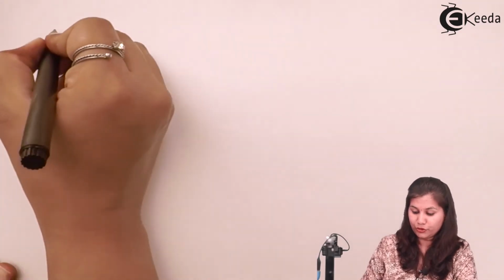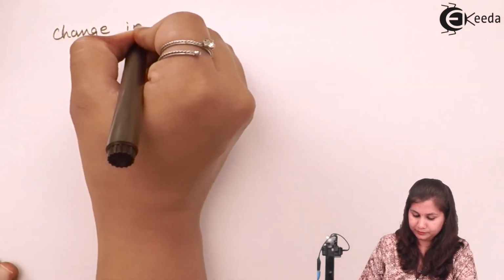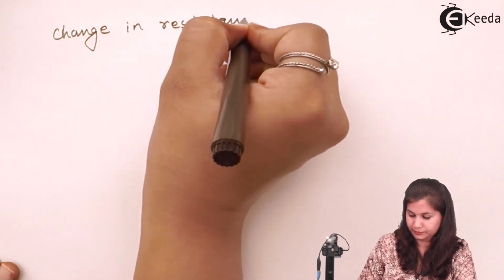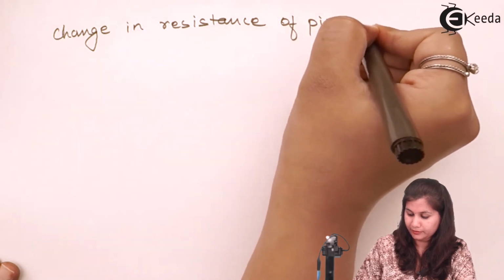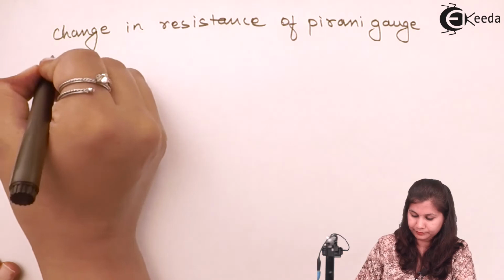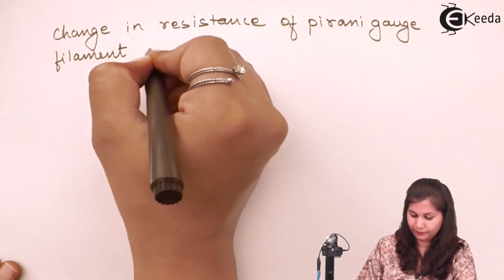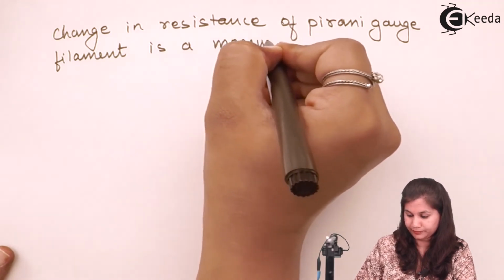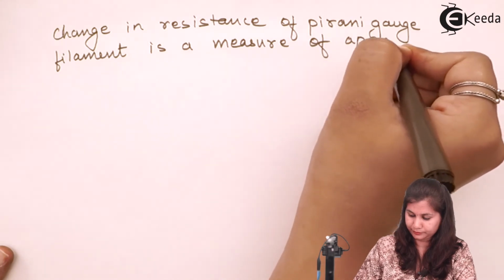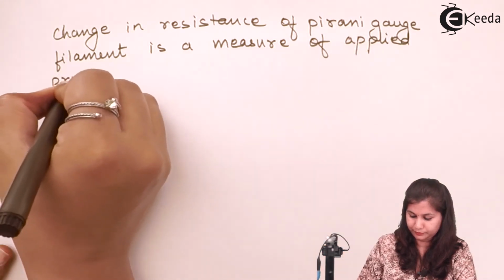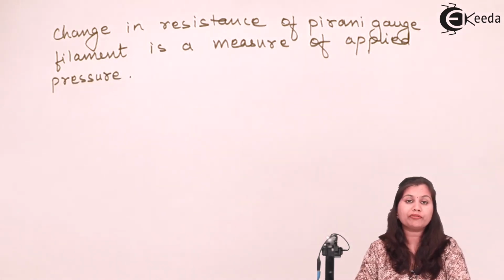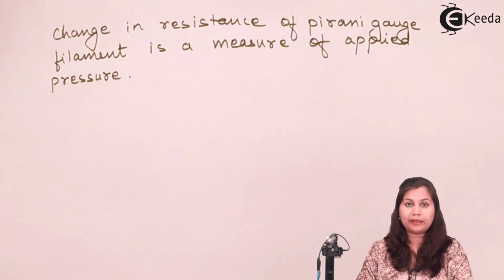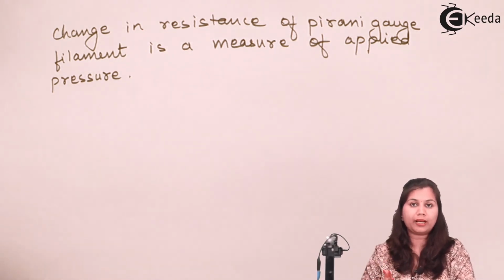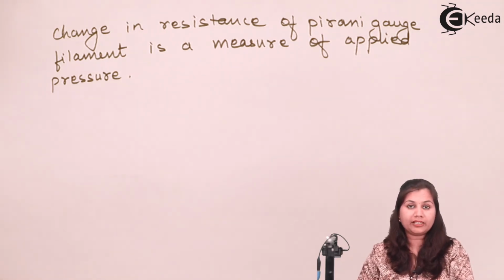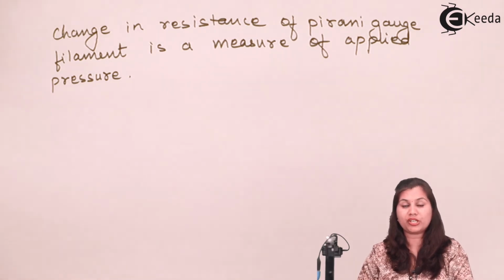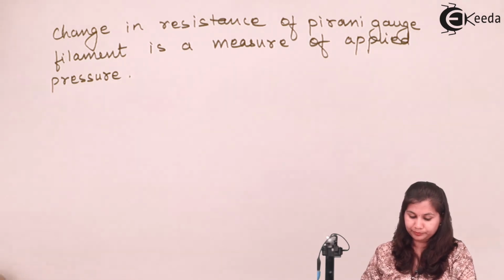And this change in the resistance is going to be measured by the Wheatstone bridge. So we can say that the change in resistance of the Pirani gauge filament is a measure of the applied pressure. If we properly calibrate this instrument, then by measuring the change in the resistance, we can measure the pressure applied on the filament. So in this way, the Pirani gauge is used for the measurement of pressure by measuring the change in resistance through the Wheatstone bridge.